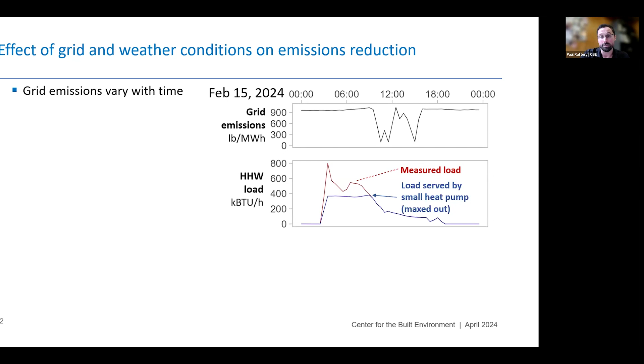You can see there's a real big dip in the middle of the day when there's a lot of solar on the grid, and that's when electricity is super clean, right? Great time to use electricity, especially if you're switching from some other fuel. Now, if we layer on the actual measured building loads, the heating loads in these real buildings that we're talking about for this demonstration, you can see what that looks like here in red. And this is the heating load, or how much heat energy is needed to heat up your building. The red line is the actual gas boiler's output, right? If we were to fully electrify, we would service that with electricity instead of gas. When we have this partial electrification case, even on this relatively mild February day, we're only able to offset a bit more than half of that load over the course of the whole day. You can see that small little heat pump is maxed out even on a mild day, and the rest of the heating capacity has to be handled by the gas boilers in that case.